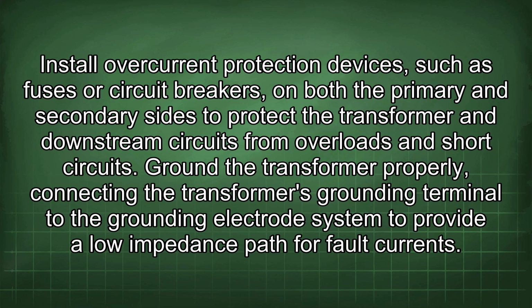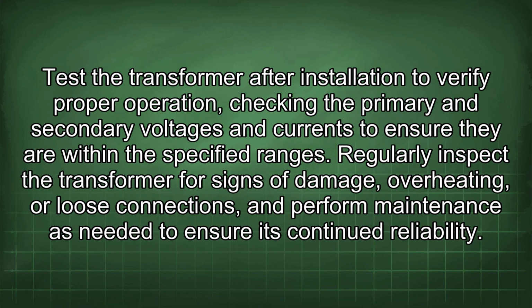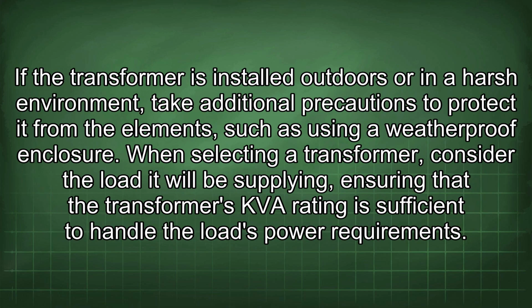Ground the transformer properly, connecting the transformer's grounding terminal to the grounding electrode system to provide a low impedance path for fault currents. Test the transformer after installation to verify proper operation, checking the primary and secondary voltages and currents to ensure they are within the specified ranges. Regularly inspect the transformer for signs of damage, overheating, or loose connections, and perform maintenance as needed to ensure its continued reliability. If the transformer is installed outdoors or in a harsh environment, take additional precautions to protect it from the elements, such as using a weatherproof enclosure.